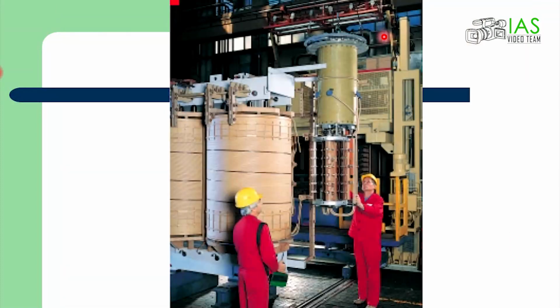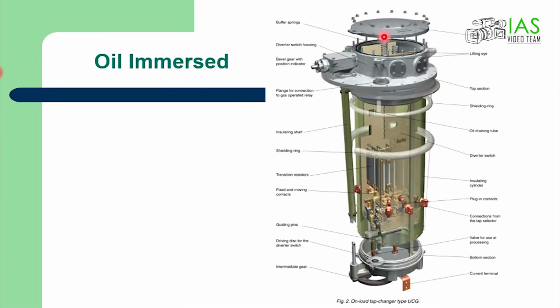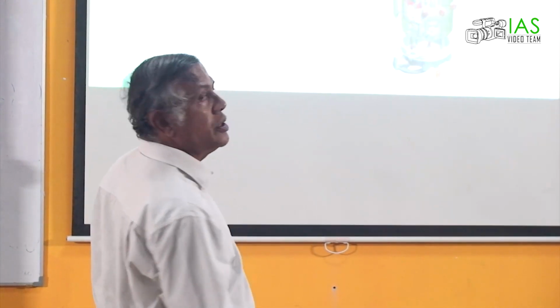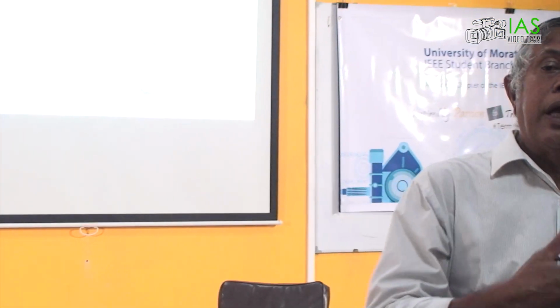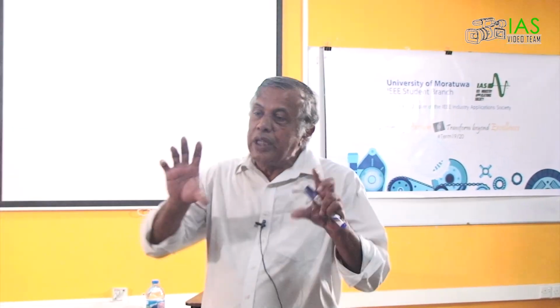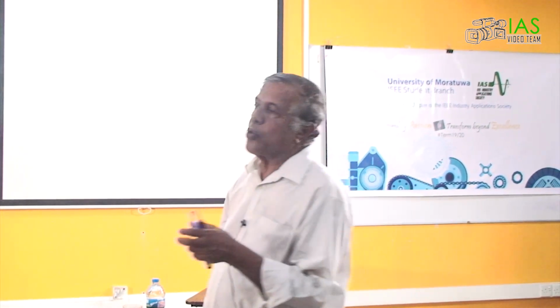This is again how it is fixed onto the transformer. The oil immersed type looks like this, and the vacuum type looks like this. Vacuum contacting of the tap changer doesn't make any arcing. It's within a vacuum breaker, like a vacuum enclosure.